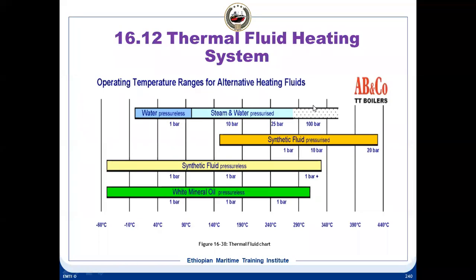The material used to build these kinds of special vessels becomes an issue. Operating at 100 bar pressure, the pumps which are rated for 100 bar pressure, plus pipelines, gaskets, the whole thing becomes just impractical. And then the systems and the components have to be designed for higher pressure with consequent strength requirements for special pressure vessels.